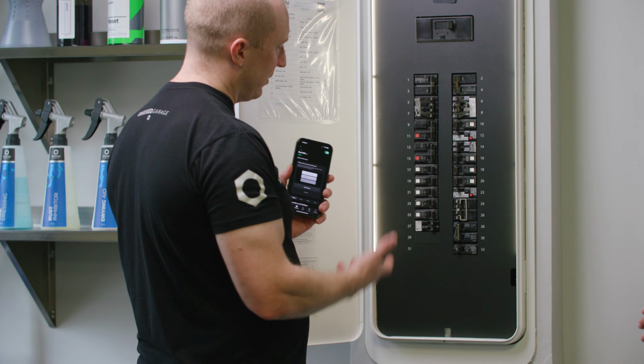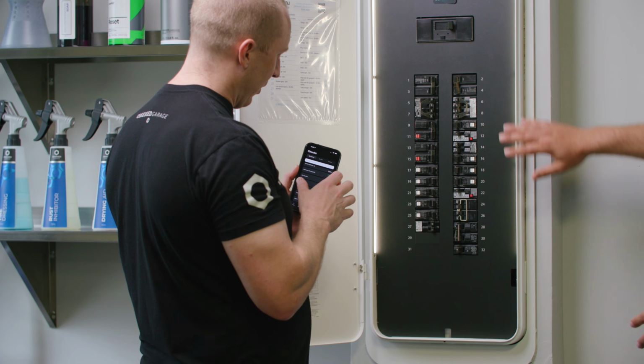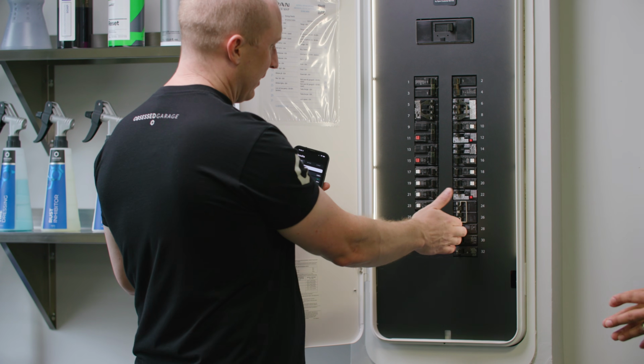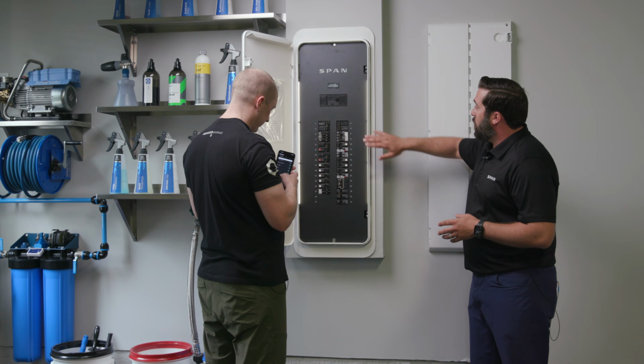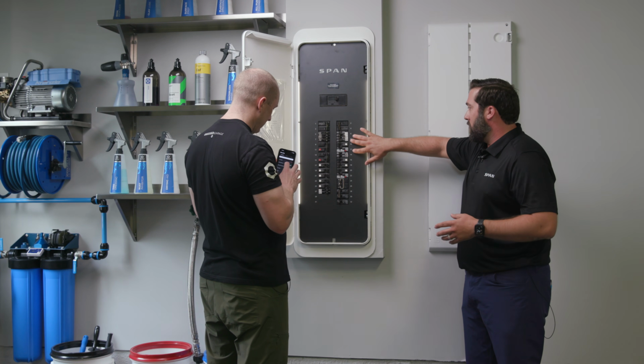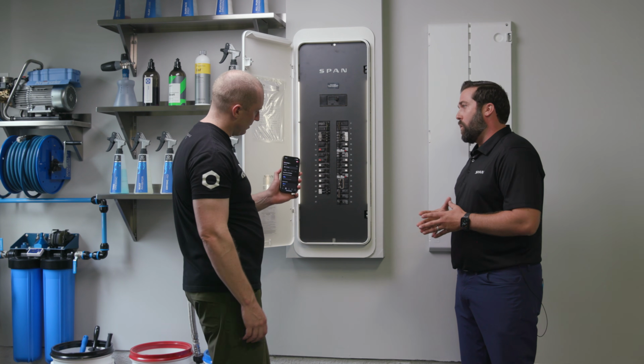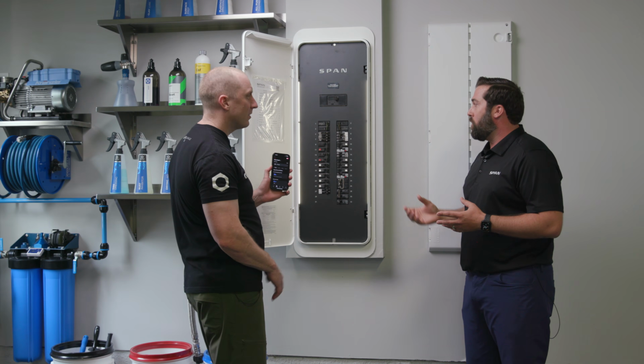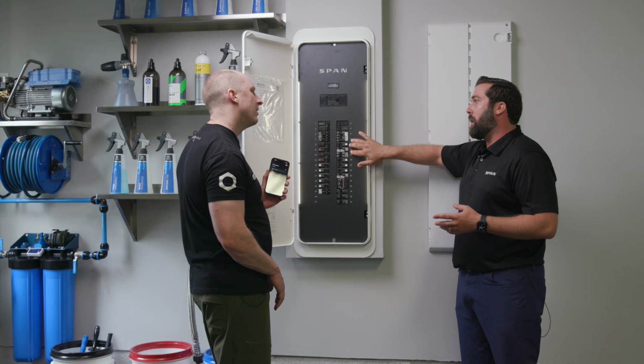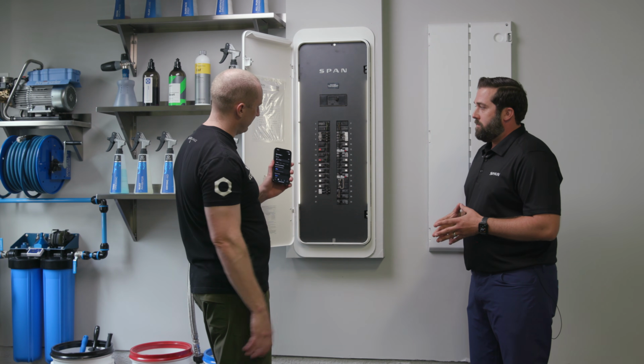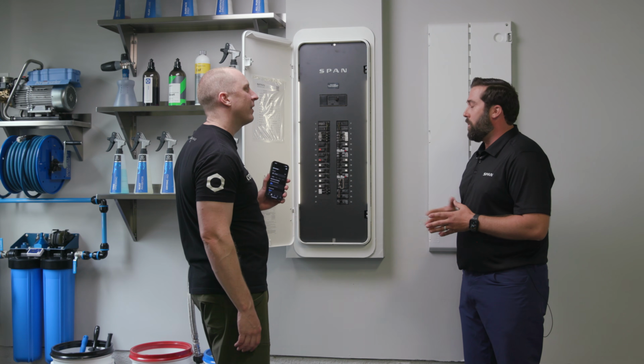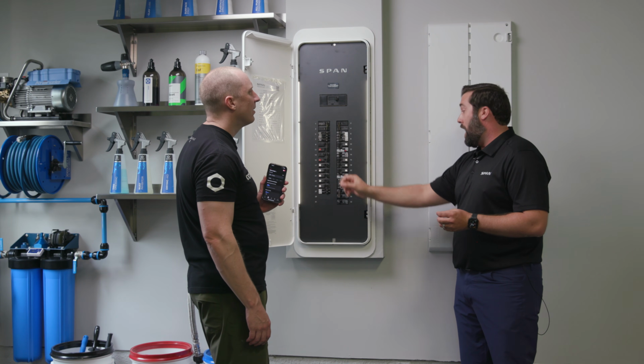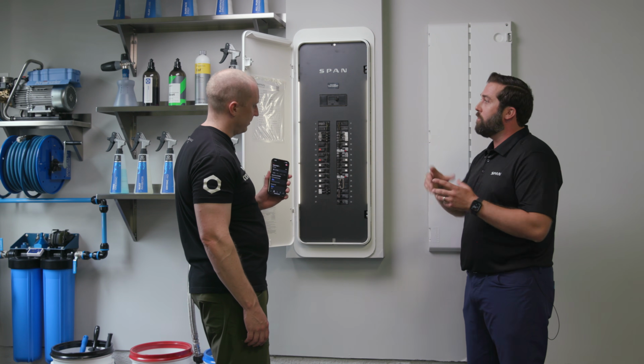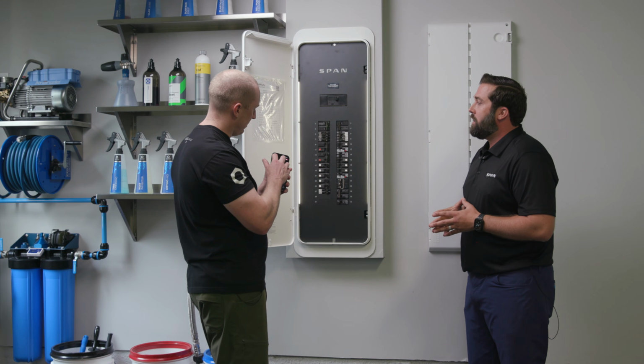Explain how that works. If I turn it on, it doesn't actually flip the breaker. Behind every breaker, every circuit as we call it, is a relay. So when we turn circuits on and off, we're essentially opening and closing relays behind every breaker. If I turn it on, you hear the click - the breaker was already on, you hear the relay close, and now you have a functioning circuit.